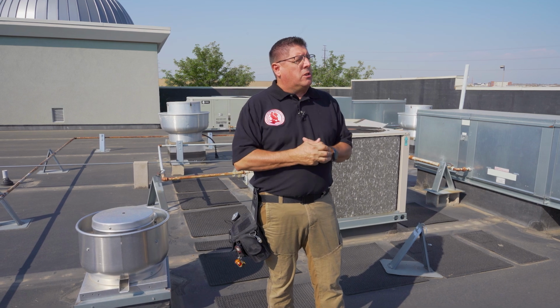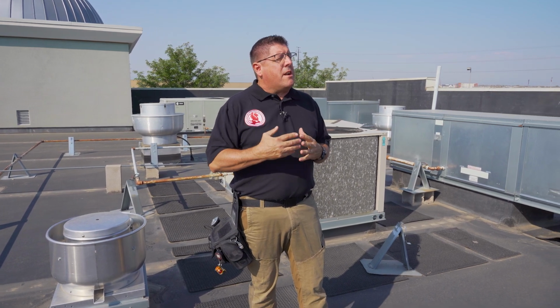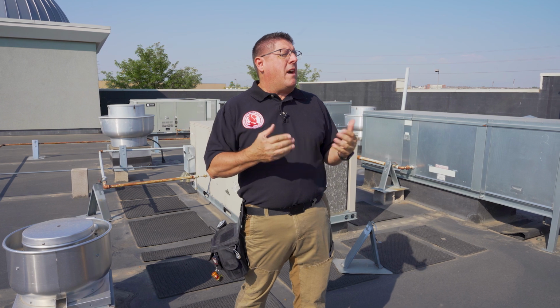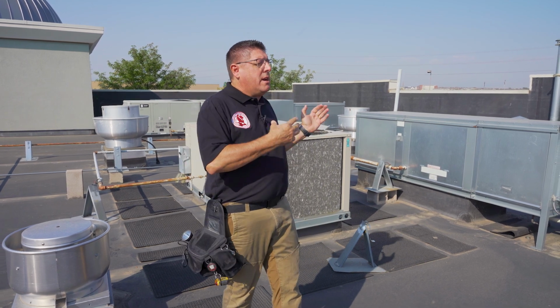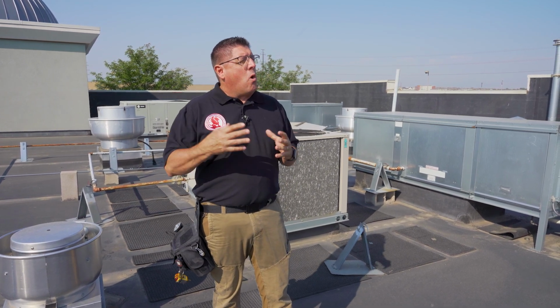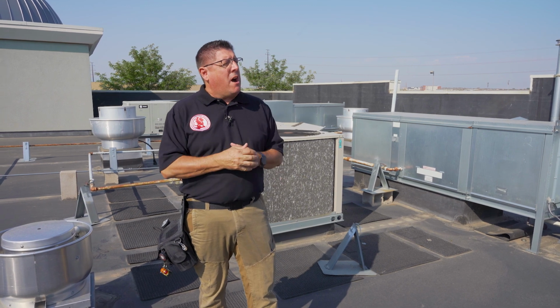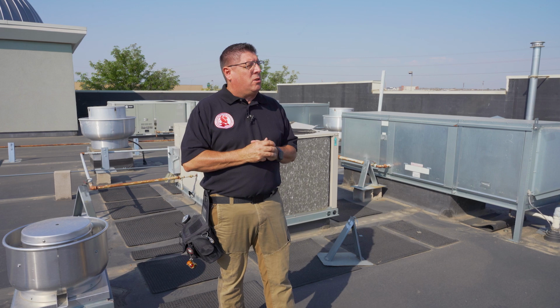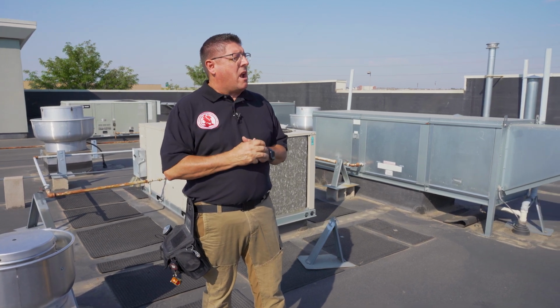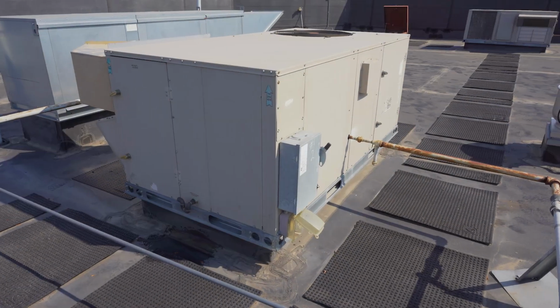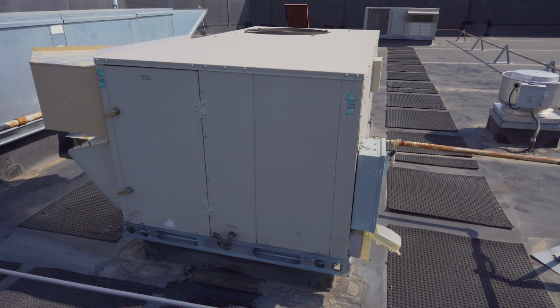Also, we want to make sure the units are accessible. Through the standard, it's very important to note that if we don't have accessible access to this, that includes a fixed ladder or catwalk for anything that's above 16 foot from the ground. Also, any roof that has a slope greater than 25% must have a level working platform in front of it. So note that. That would be a reason why that unit would be inaccessible, and you are required to identify any units that are inaccessible for inspection. Beyond that, we want to operate each unit and make sure that they work.